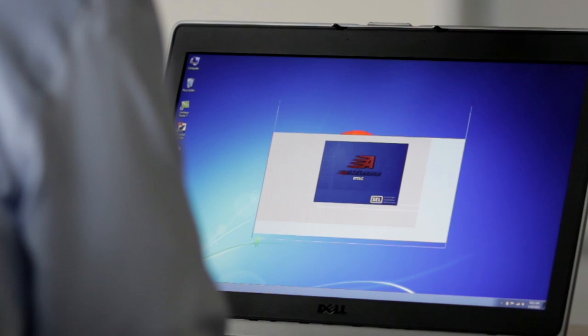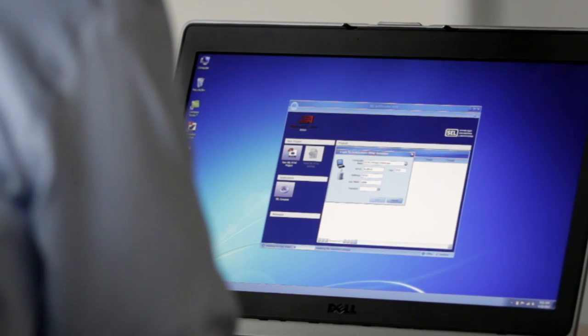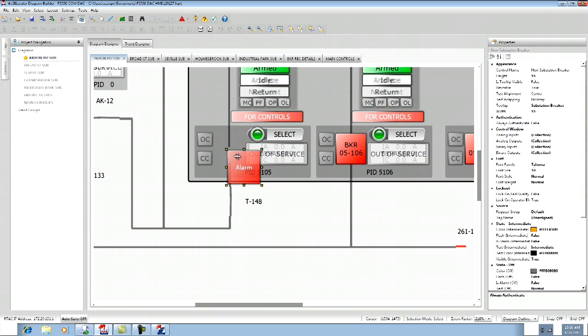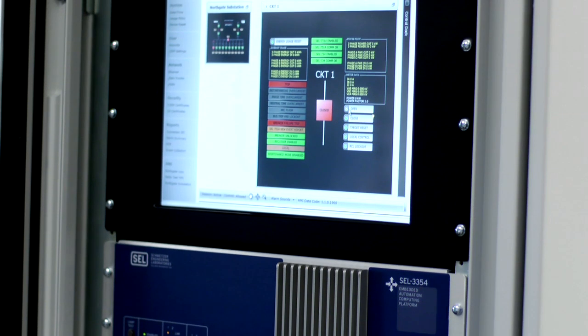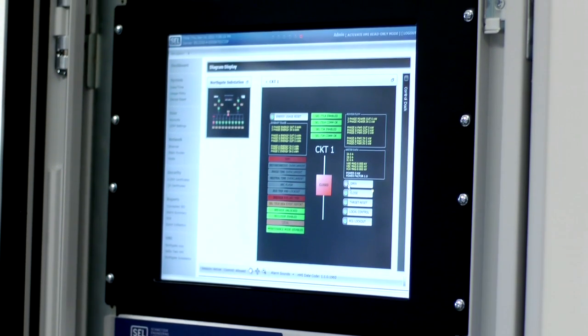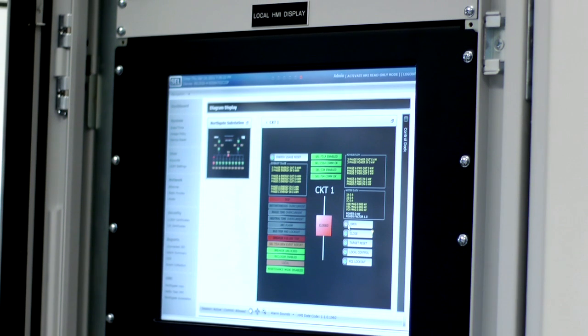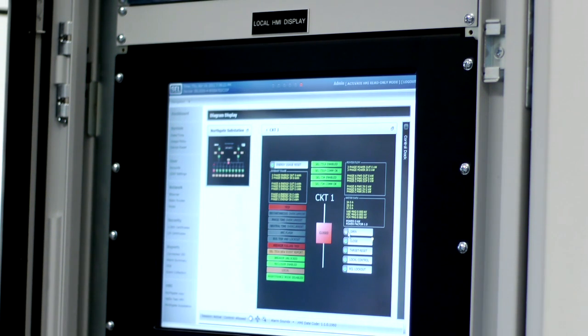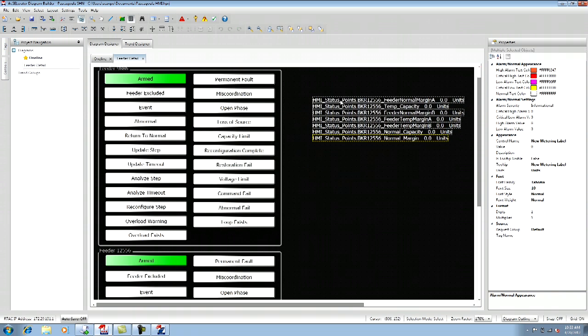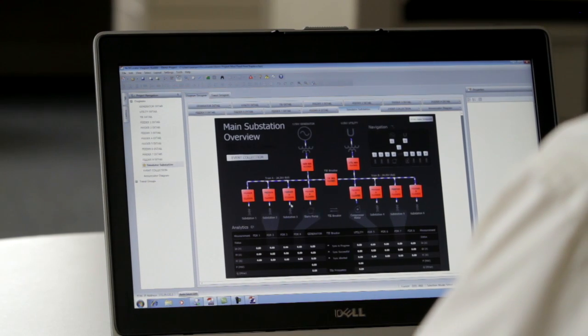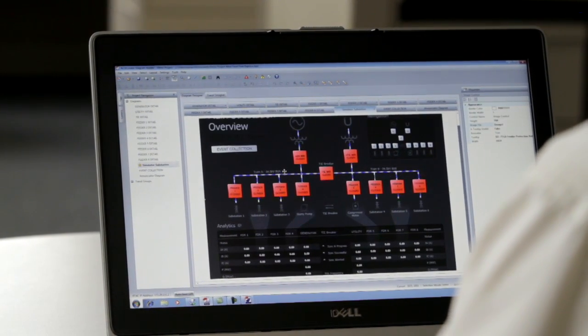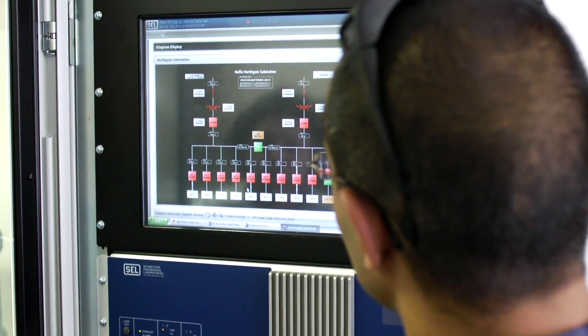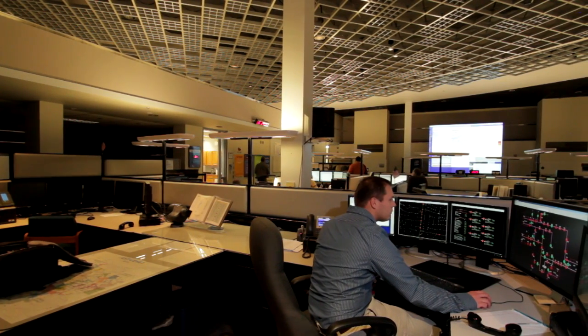Recently, we released a brand new web-based HMI capability for the RTAC along with the configuration software to design the visualization screens called Diagram Builder. This is a really beautiful and simple solution because all of the screens are hosted directly from the web server on the actual RTAC in the substation. It's a web-based HMI which allows an end user to quickly grab points, define those points onto a screen, and present those in a quick and easy manner for anything from a small substation up to where an operator wants to see alarms or status symbols from the individual relays.